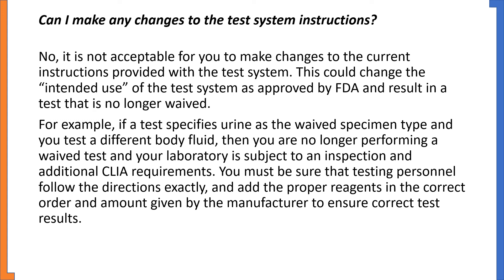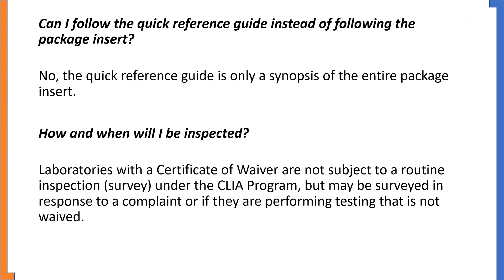You must be sure that testing personnel follow the directions exactly and add the proper reagents in the correct order and amount given by the manufacturer to ensure correct test results. Can I follow the quick reference guide instead of following the package insert? No, the quick reference guide is only a synopsis of the entire package insert.